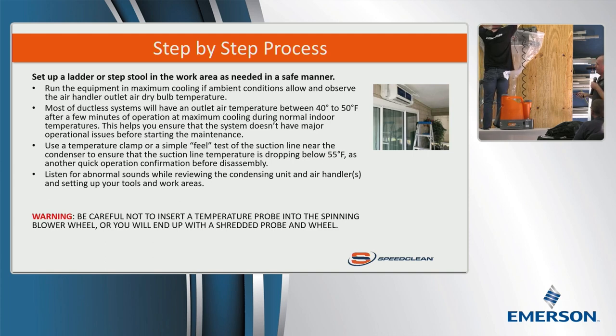You need that discharge outlet air temperature to be between 40 and 50 degrees typically. A feel test on the suction line is generally acceptable. You want to ensure your suction line temperature drops below 55 degrees Fahrenheit. If it's staying above 55 degrees, there's basically no circumstance, other than maybe the most extreme, where you should see a suction line on a ductless system floating above 55.